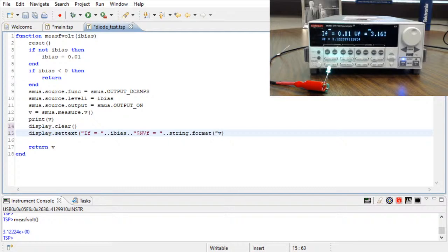So there's some documentation in the manuals again, but in the Lua reference manual, actually, I think it's maybe a little light in our own reference manuals, but the Lua reference manuals can be pretty handy if you want to do some complex formatting. Or you can just Google the C sprintf command, and it supports all the typical ones. So now what this means is that we're going to use the engineering notation, little e, and we're going to use 1 digit. Actually, why not change it to 2 significant digits there.